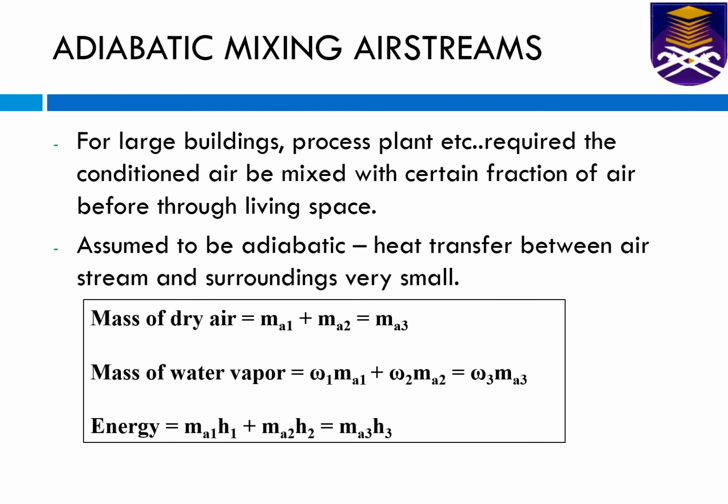If you look at those 4 processes before, for example cooling, involving the cooling coil or the evaporator, then heating, involving the heater or condenser, those parts involve a lot of electricity bills. So another innovative way to reduce the power and energy consumption is to mix a flow, a co-flow that has been processed, and then bring it back together with the atmospheric air.